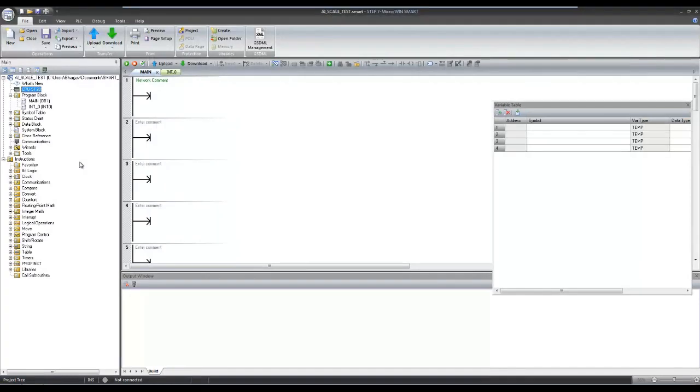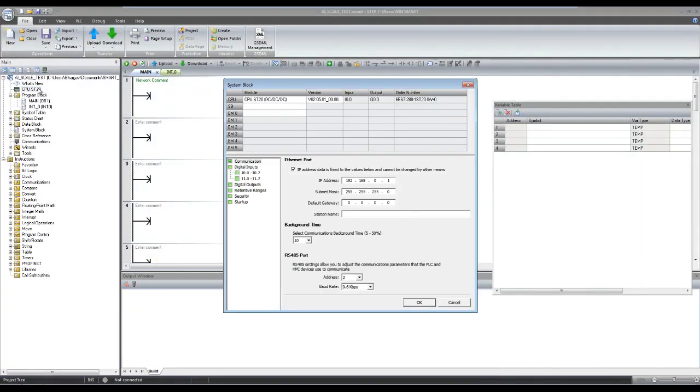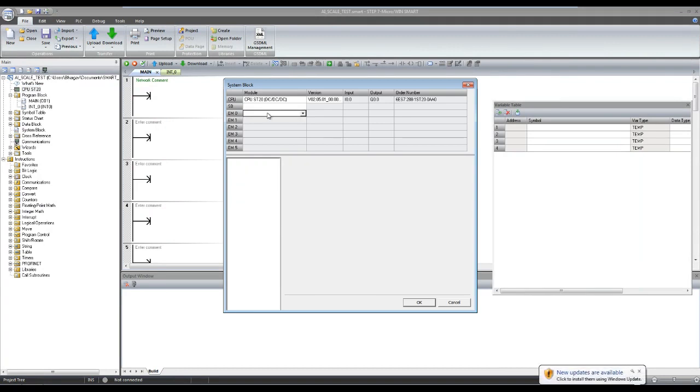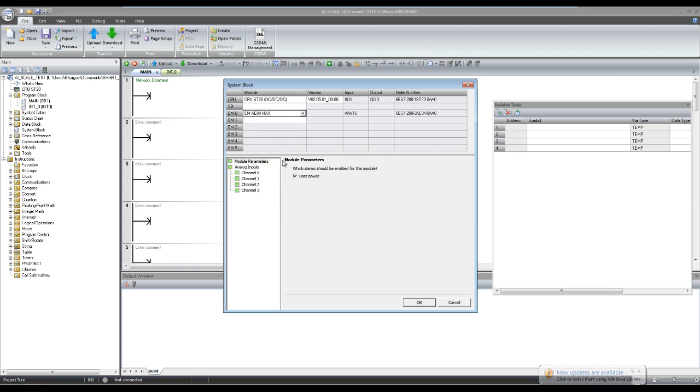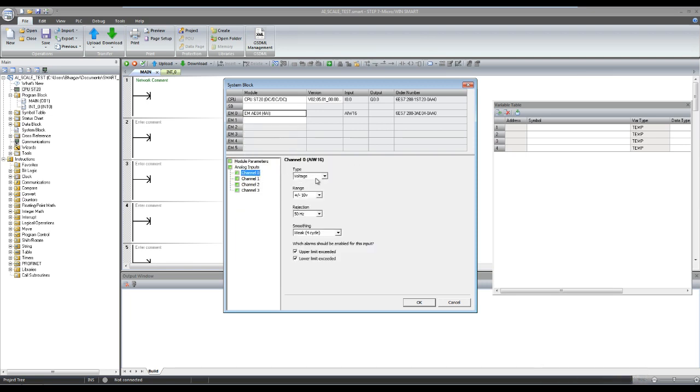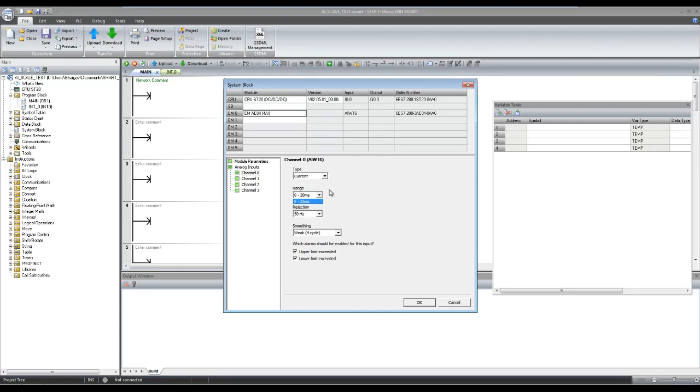Now let's start the configuration. Configuring analog module in hardware configuration. If you select input signal type as current for channel 0, then channel 1 can be used with current signal only.